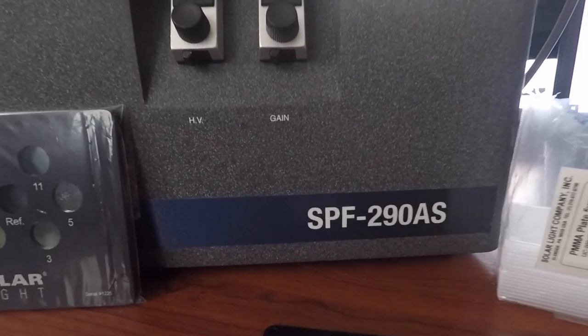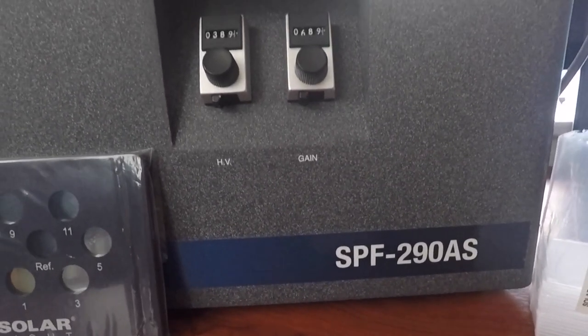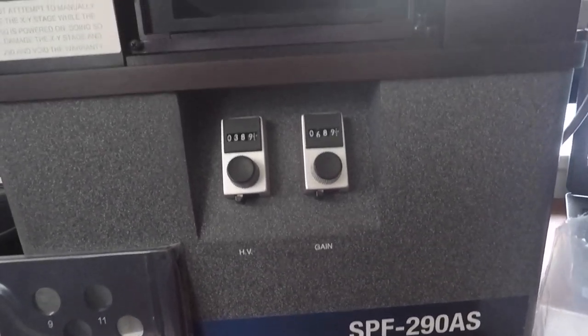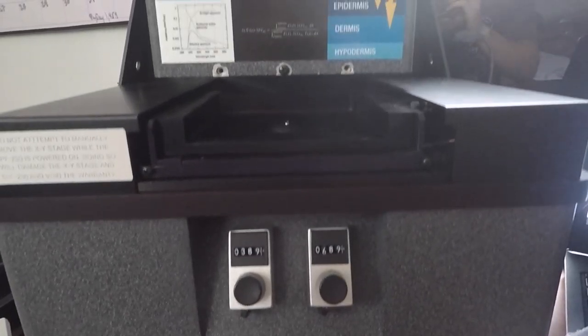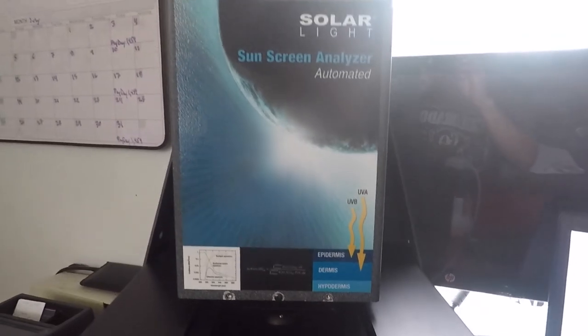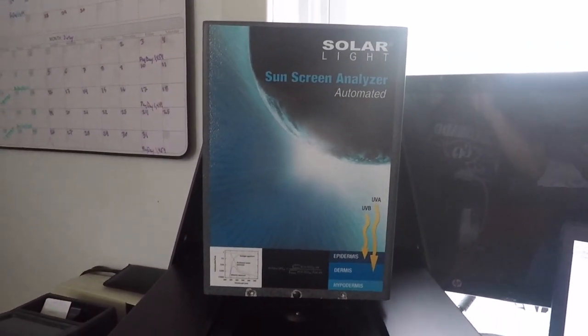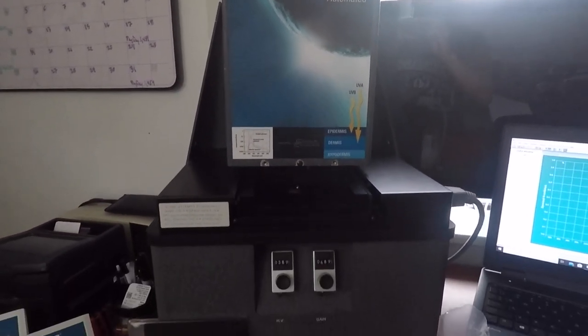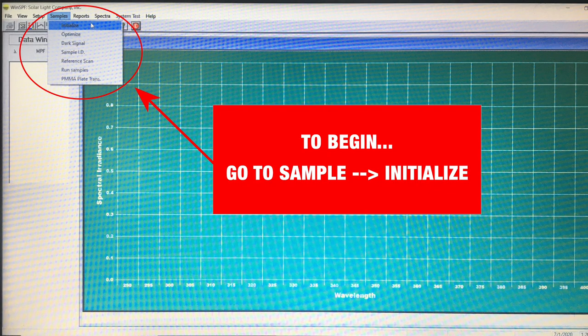Upon startup, some of its flagship features, like its automatic stage and its internal monochromator, are optimized for each session. The automatic stage will not only save us the hassle of repositioning samples, it will provide the speed and precision that is necessary for certain time-based studies like photobiology and photostability. Even more, some tests require 9 back and forth adjustments just to complete their scans, so our stage is going to guarantee that there's reduced overhead costs.